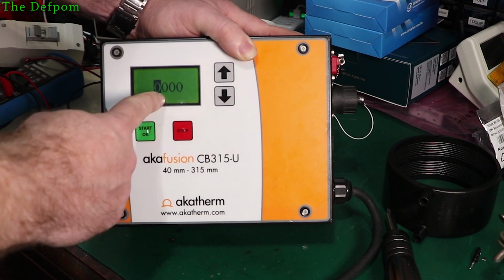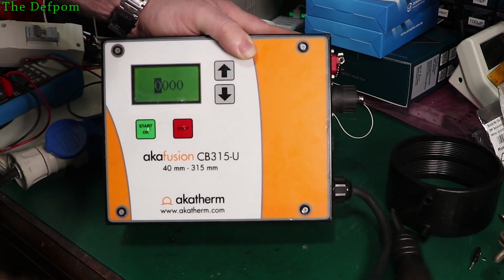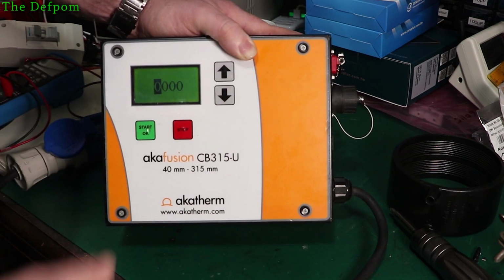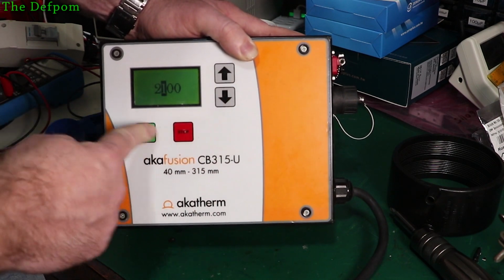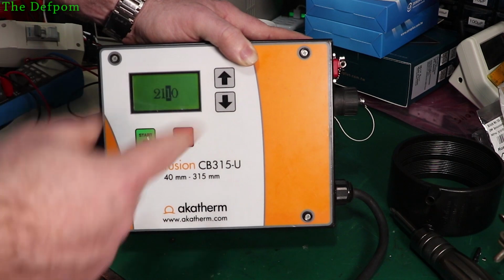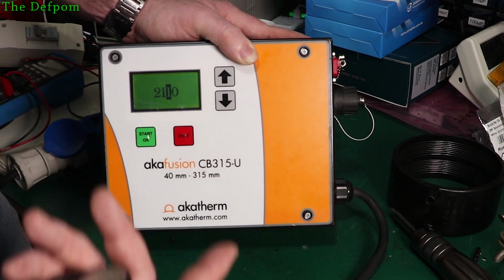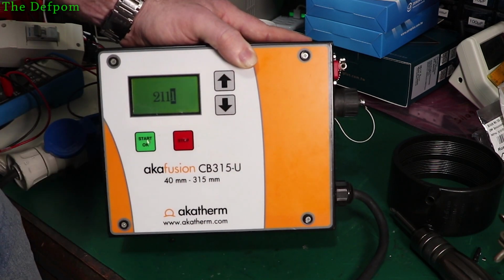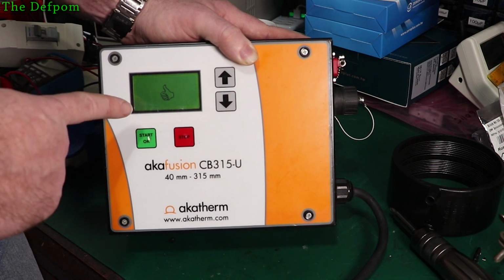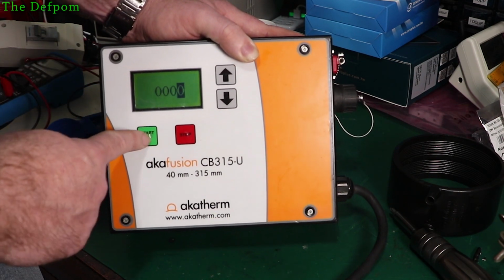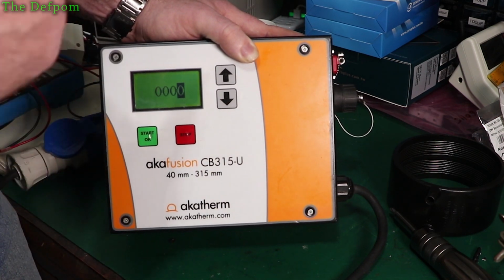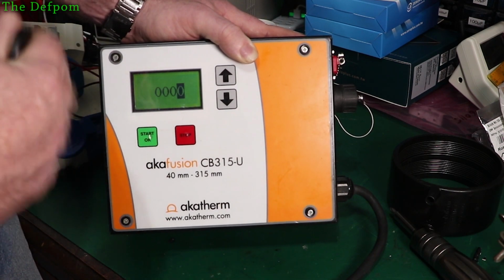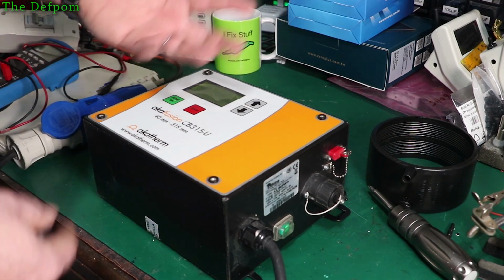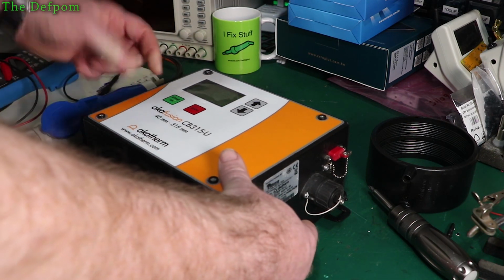Now, one of the menus says 2110, which is to reset the print flag, or well, the welding history, the reports. Right, it does a report for each weld apparently, stores them up. So you can reset that using 2, 1, 1. Right, it's supposed to reset the welding flag. So, well, I was looking at the code. It's got 1000 series, there's a couple of things, and you've got 2000 series just by itself. Thinking, okay, well, let's try another random code. So let's put in 211, an extra 1 on the end, which isn't documented. It does something. Don't know what. If it's an invalid code, it says that. So 2111 does something. I've got no idea what it's doing, but I think it's resetting something. You know, doing 2111 hasn't reset the maintenance menu. The maintenance alarm still comes up.